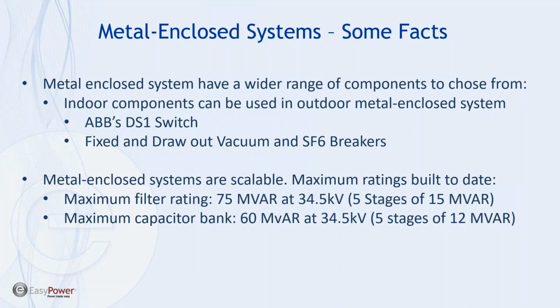If you need 75 megavars, we're going to break them up into stages. The same thing has to be done with open air solutions. The primary constraint in capacitor bank or filter bank size is the switching device and also the reactor rating capability. So NEPSI has built systems as large as 75 megavars in a single enclosure. I showed you a picture earlier of 5 stages of 15 megavars. And we've also built capacitor banks up to 60 megavars at 34.5 kV.